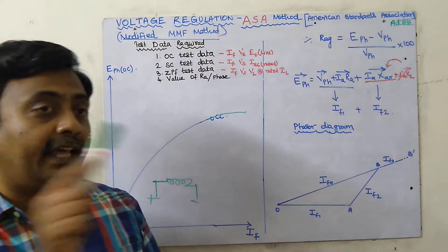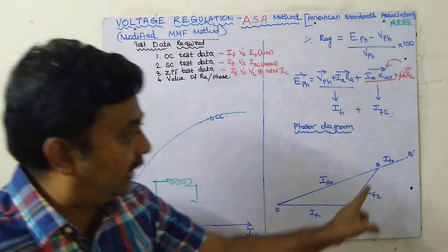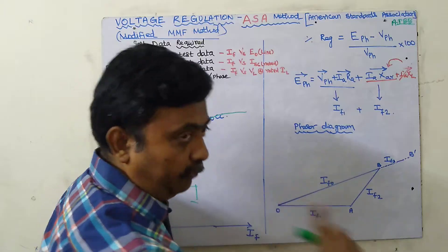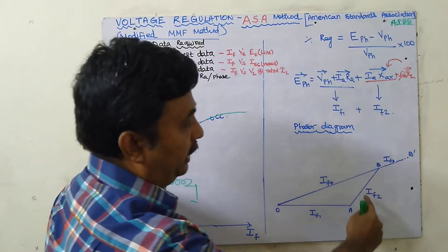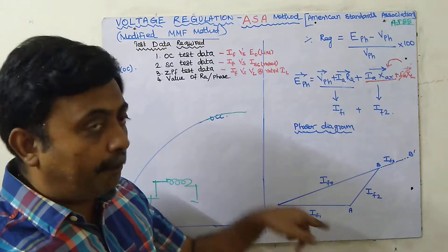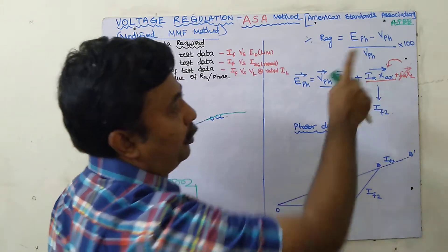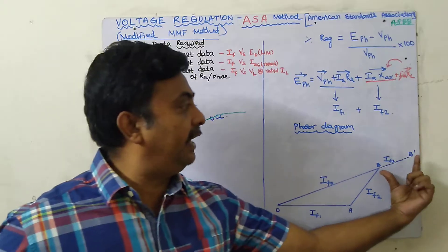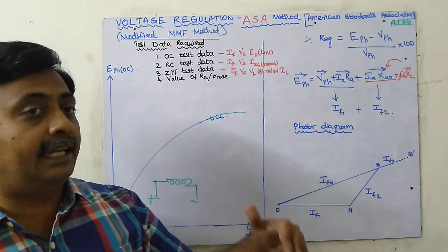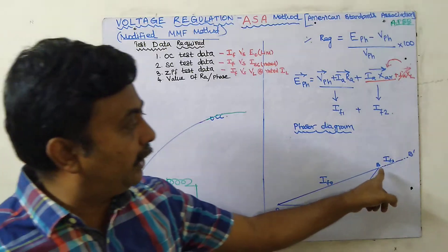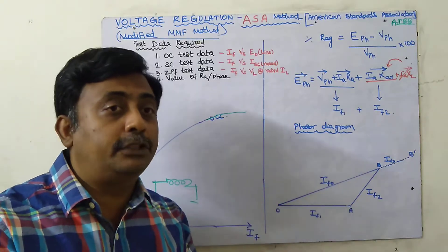This magnetic saturation is not taken into account in the MMF method, but in this modified MMF method — the ASA method — it is also taken into account. We have IF1 as one field current and IF2 as another. IF1 is required to produce rated voltage and overcome armature resistance drop; IF2 is to overcome armature reaction drop. We add the two to get IF0, but we must also add an extra term BB-dash, which is IF3, to account for magnetic saturation. We should also know the procedure of the ZPF method.